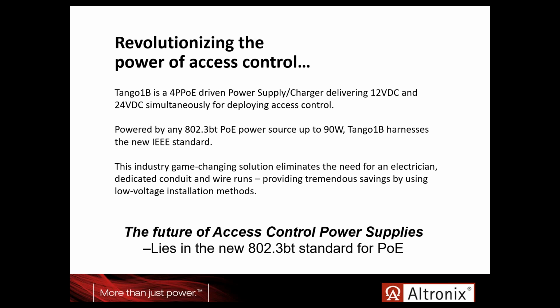So we're talking again about the power injectors or mid-spans, the Netway 4BT, for instance, from Altronix, the Netway 8BT, that will be located in an IT rack. We will have Cat 6, or Cat 5e technically, or higher cable plugged into it. We'll go 100 meters to this Tango board, which would be located in a power supply enclosure, one of our Trove access and power integration enclosures, and it will be able to deliver both 12 and 24 volts DC simultaneously for access control devices.